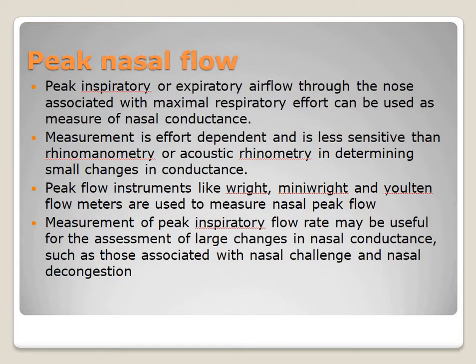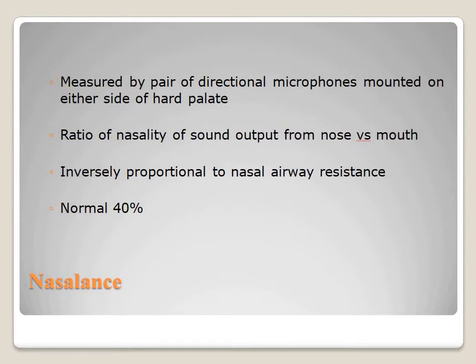Peak nasal flow: the peak inspiratory or expiratory airflow through the nose, associated with maximal respiratory effort, can be used as a measure of nasal conductance. The measurement is effort-dependent and is less sensitive than rhinomanometry and acoustic rhinometry in determining small changes in conductance. Peak flow instruments such as the Wright, Mini-Wright, and Youlten flow meters are used. Peak inspiratory flow rate is useful for assessing large changes in nasal conductance, such as those associated with nasal challenge and nasal decongestion.